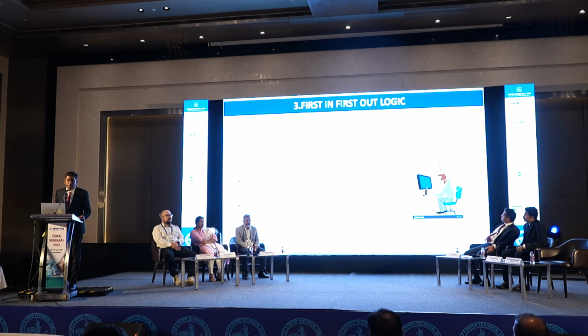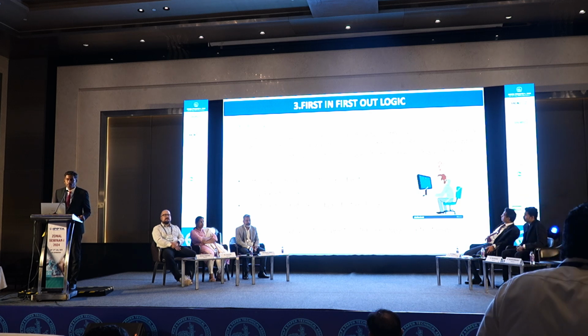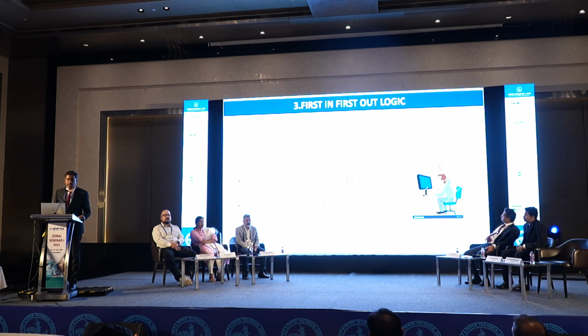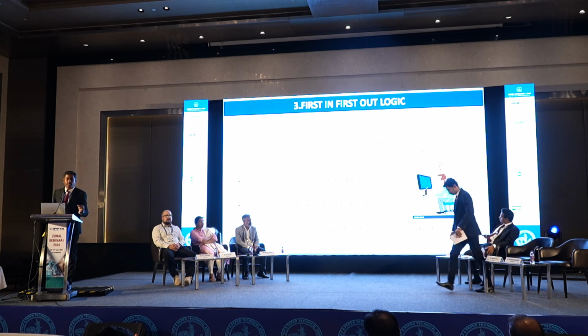It's a troubleshooting case. We all know the FIFO block very well. What does it represent? It's first in, first out. So how and where to implement it in DCS is our beneficial purpose. In DCS, we use a lot of pumps and valves. For safety purposes, we use multiplexers and a lot of interlocks. In such a scenario, we face the problem that a pump or equipment failure can have many possible causes.